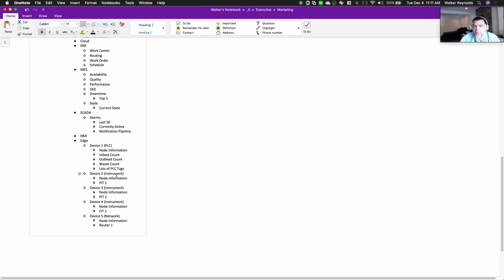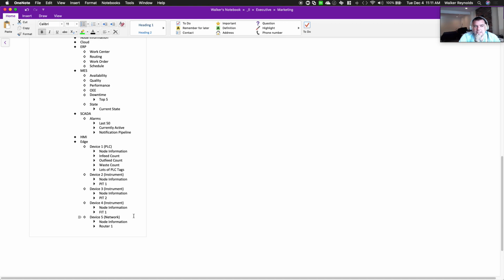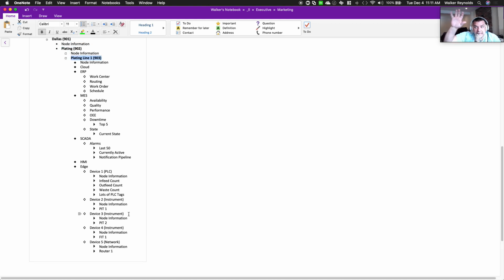So device 2 is an instrument - would have node information, and it would be pressure transmitter 1, and it would contain everything: scaling information, health of the instrument, how long it's been running, all that kind of stuff, and obviously the values. We could do configuration by writing a value back into this namespace that then sets our instrument up. Device 3 is an instrument, pressure transmitter 2. Device 4 is an instrument, flow transmitter 1. Device 5 is a network device - actually a router. So this is the idea of the namespace, the unified namespace for the organization.